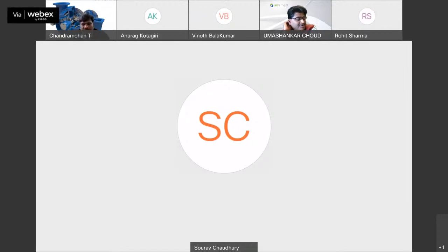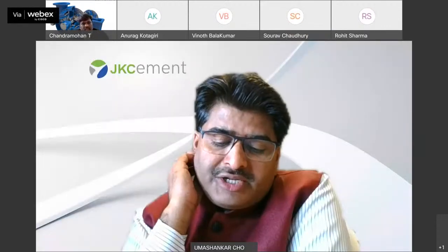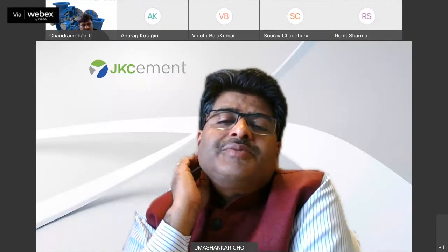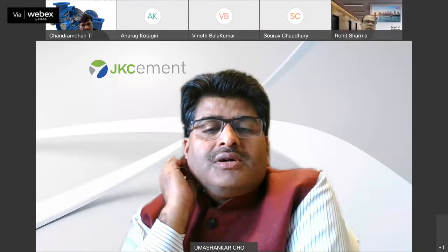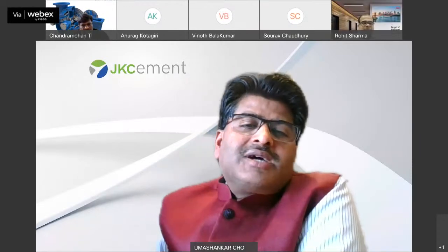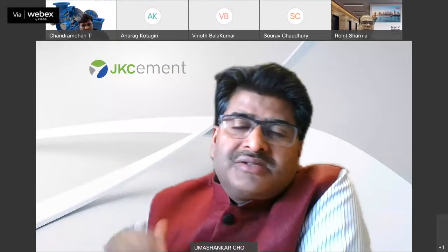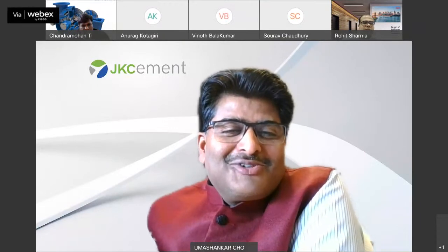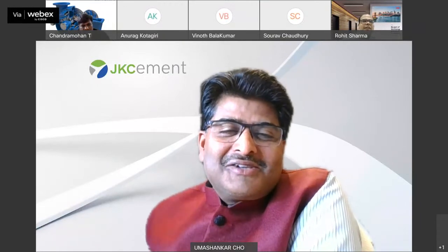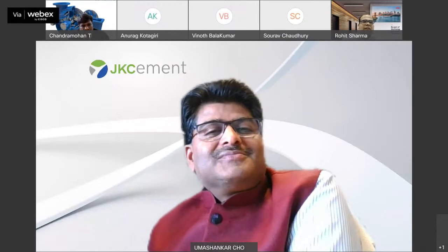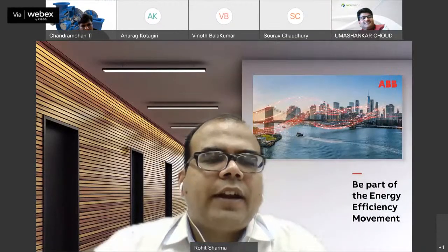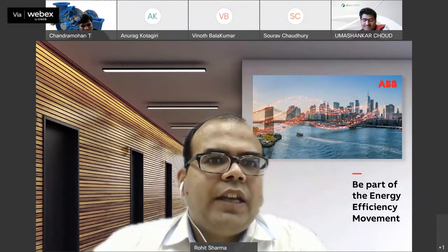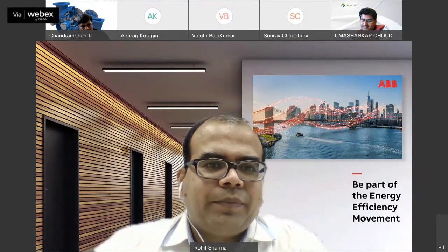Rohit ji, one more question for you. As you are talking about the advancement of SPRS technology, can this work at less than 60% speed also? Because sometimes if a plant is disturbed, it has to run at less than 50% of speed, and at that time also power saving through the SPRS system is required. So is it applicable or not? Sir, it is applicable. Basically, this depends on our rotor voltage. The lesser the rotor voltage, the wider the operating speed range.